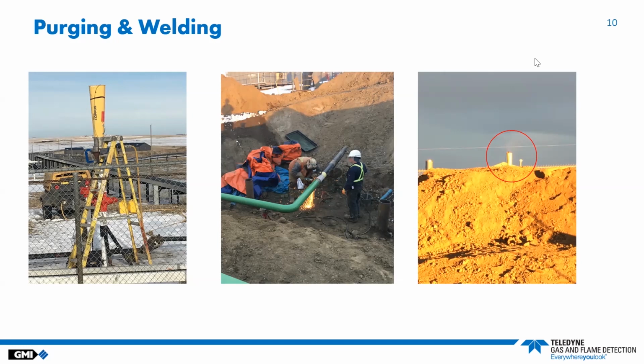If you are purging with pressure above ambient pressure, it is recommended that you place a one-way valve with a T-piece in line of the sample tubing to reduce the pressure entering. The 700 series has a pressure sensor fitted on the pump, having a max flow rate of 0.5 to 0.7 liters, which will result in a sample flow fault in the event of a high pressure situation. The pump and the pressure sensor are fitted before the gas sensor, therefore protecting the integrity of the sensor performance and construction, offering the operator reliable and accurate gas reading.